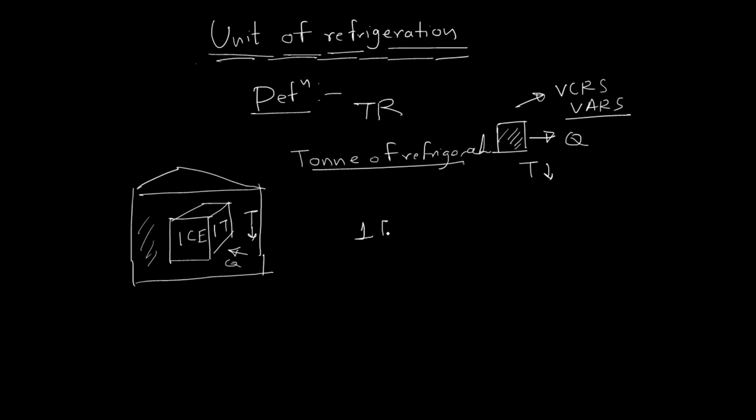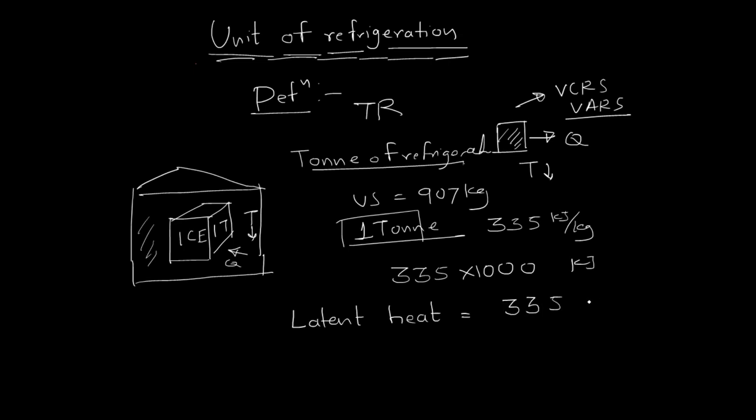Suppose we bring one ton of ice into a room, and we know latent heat of ice is 335 kJ per kg. That means from the room it will take 335 times 1000 kJ of heat. But this is not a metric ton - this is a US ton, which is equal to 907 kg. Therefore, the latent heat taken from the room will be equal to 335 kJ per kg multiplied by 907 kg.